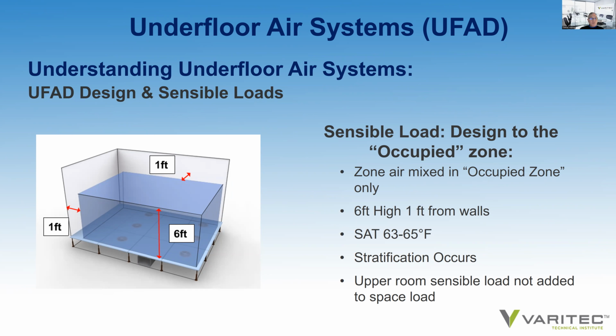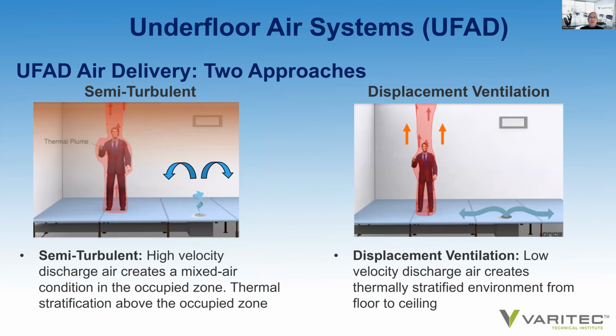One thing you do have to be aware of is the orientation of the building and where the rising and setting sun is in relation to the floor panel and the consequent radiant effect of a sun showing on a floor. That would have to be taken into an engineer's evaluation of load calc, but it's something that should be addressed, and it shouldn't present a problem if it's considered during design phase.